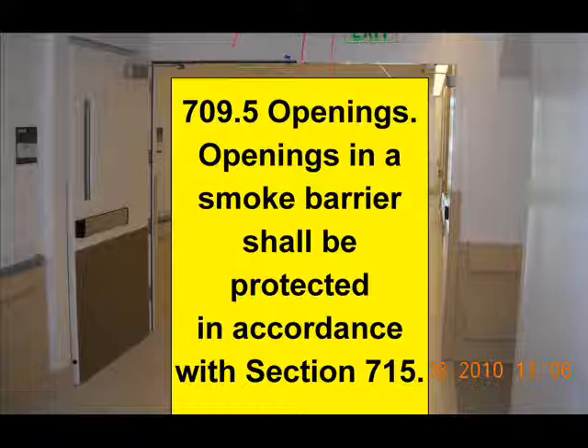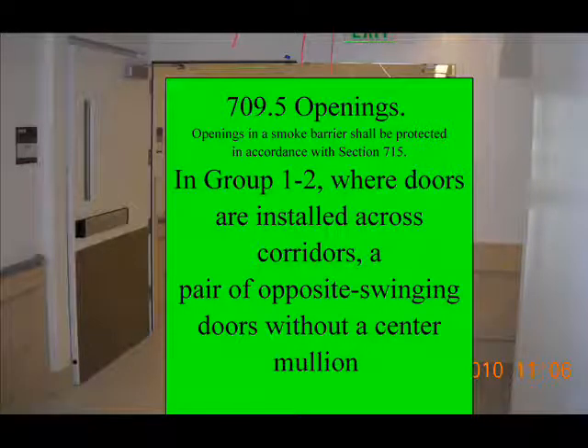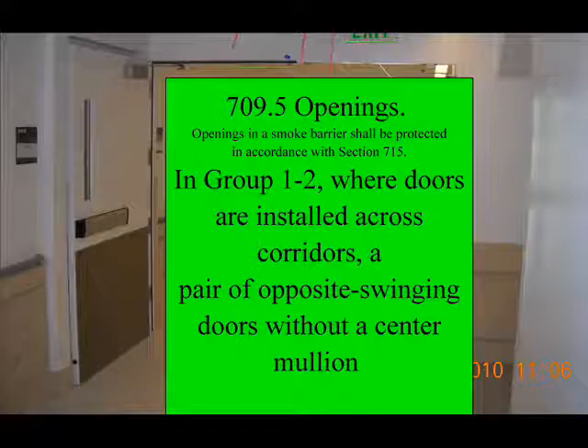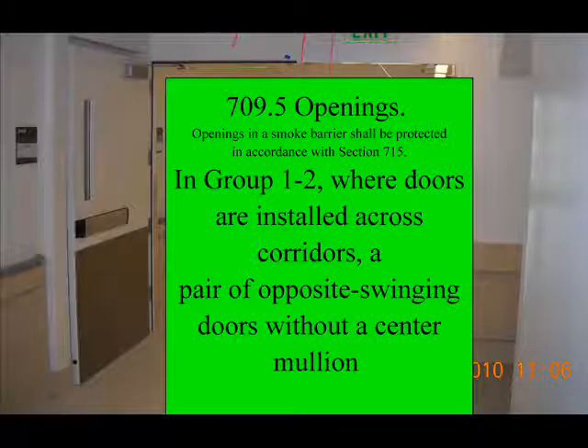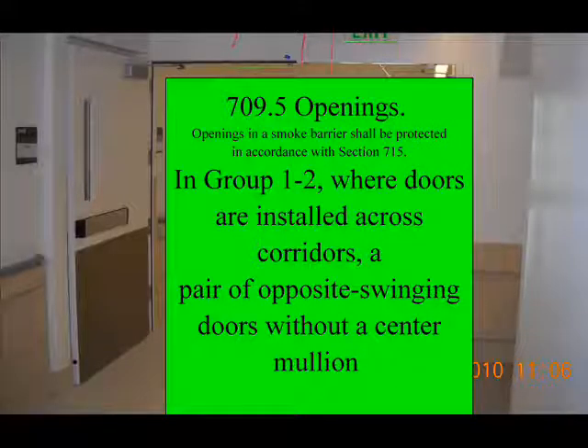We're looking at chapter 7 and we're going to get all of our answers. Notice that we've got a pair of doors right here. This is a corridor, and this happens to be a smoke barrier that we're looking at. Within about five minutes, you'll know about the door swings. Here we go — 709.5: in Group I2, where doors are installed across corridors, a pair of opposite swinging doors without a center mullion are required.